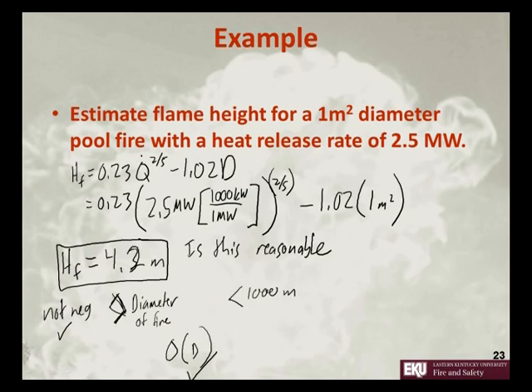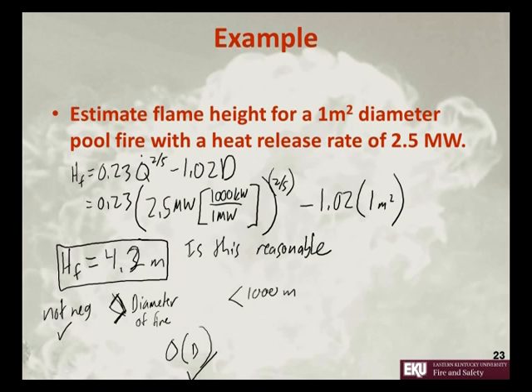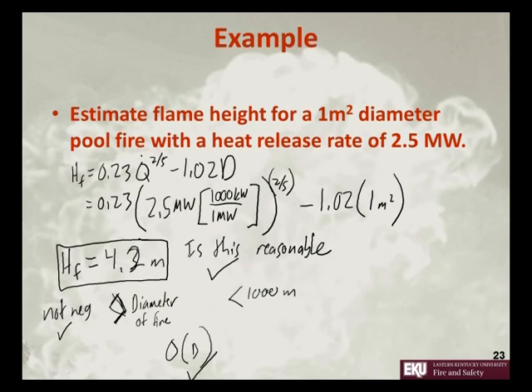We want it on the same order of magnitude — we don't want 100 meters or 1,000 meters. 10 meters, maybe. But generally, we'd want it less than an order of magnitude larger, because if it were 10 meters the Froude number would be really large and it would be more like a spray fire rather than a pool fire. So is this reasonable? Yes, I think it is.